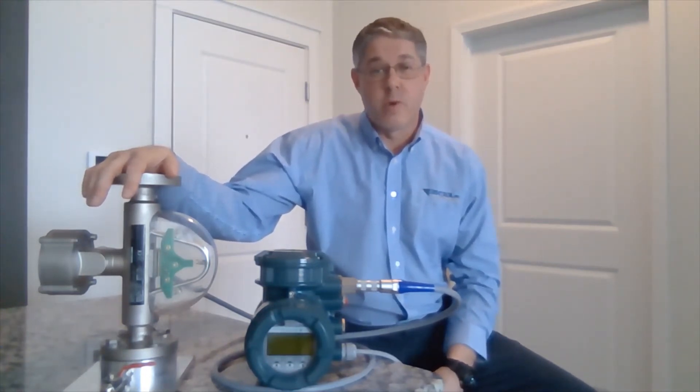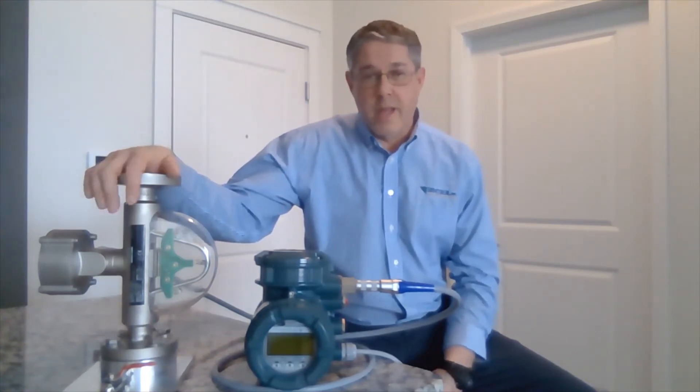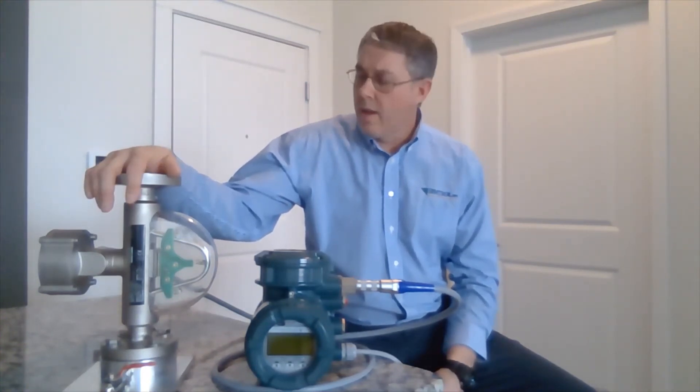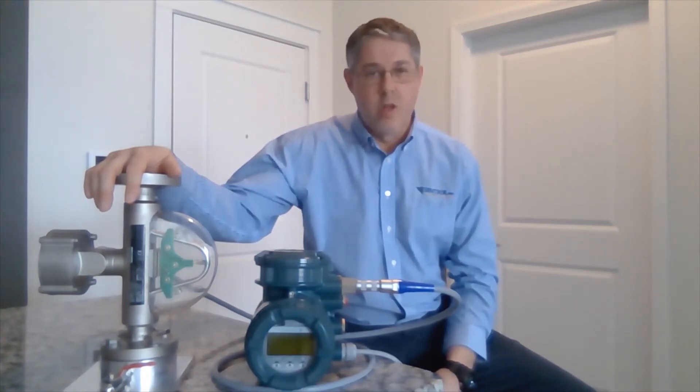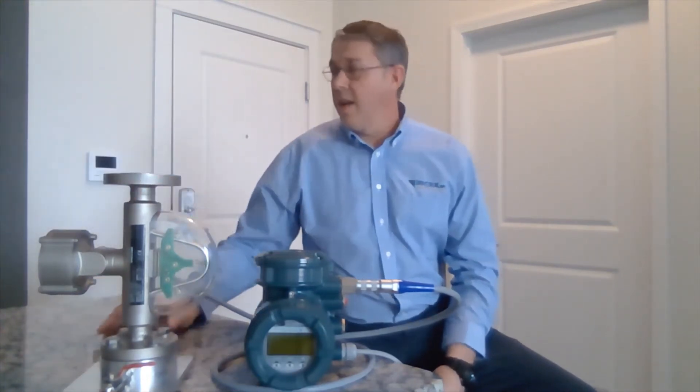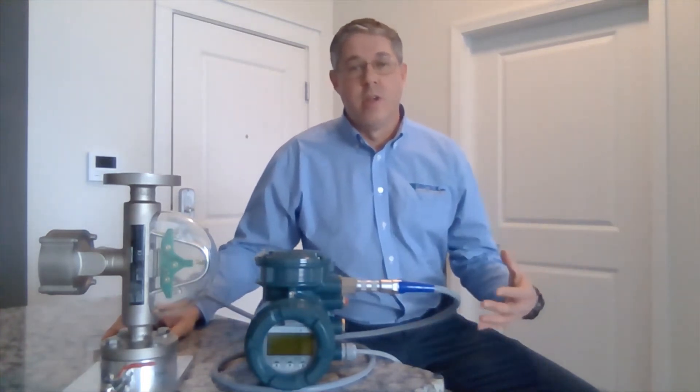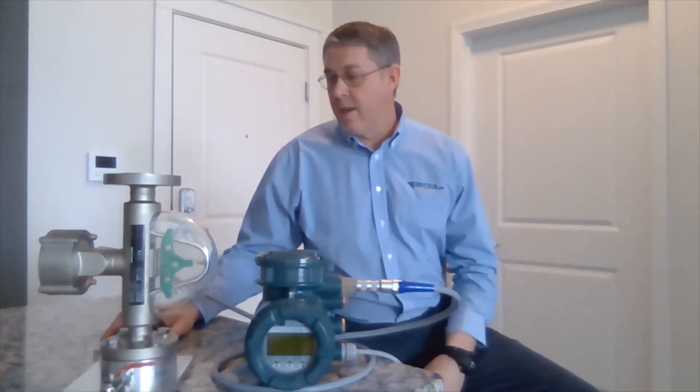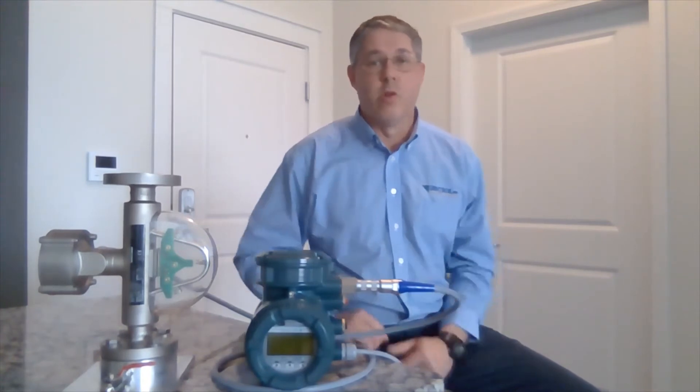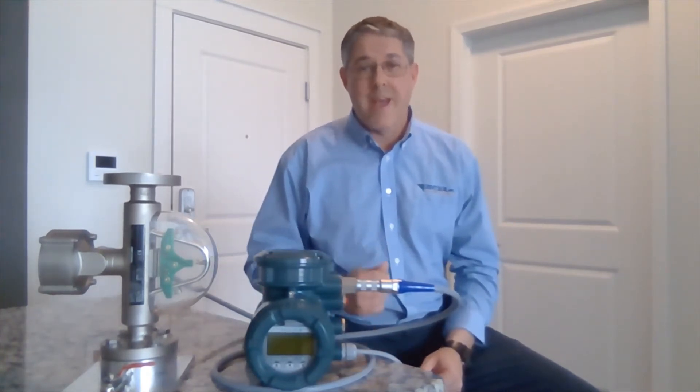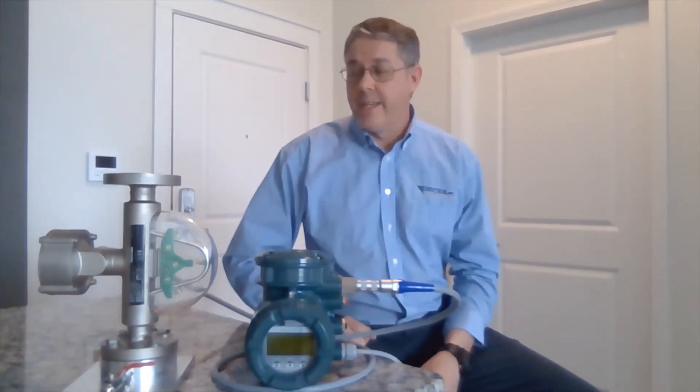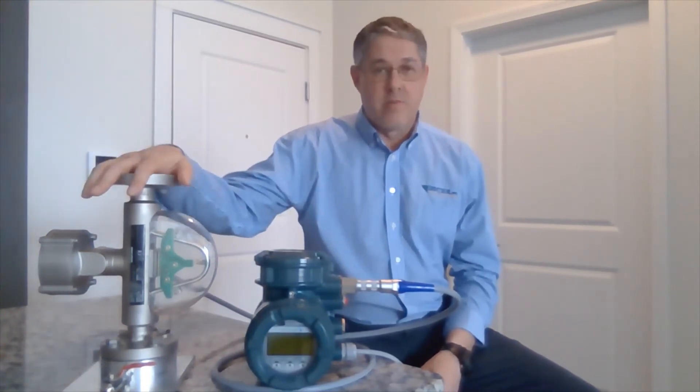You can do bi-directional flow with a Coriolis meter, and Coriolis meters typically can handle a very wide range of pressures and temperatures. The biggest benefit for a Coriolis meter is you're getting a true mass flow, temperature, and density measurement out of one meter.